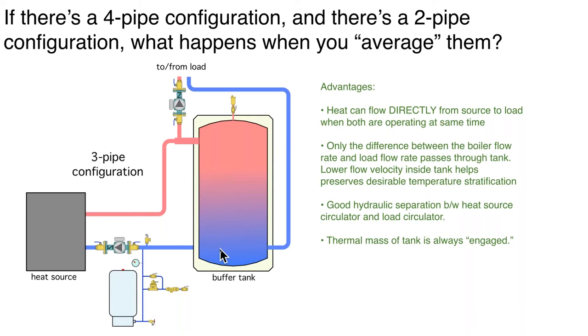So if you're going to control the heat source based on room thermostats rather than tank temperature, don't do a two-pipe — do a three-pipe buffer. We can still get good hydraulic separation with this.